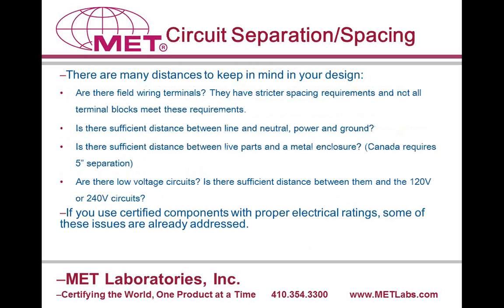Now, part of your design will include what's called electrical spacing. That's the separation between your live parts, your live and neutral, your live and ground. There needs to be a certain distance between these components. If you have a field wiring terminal, the spacing requirements tend to be greater because of the possibilities of loose wires. And this is one of the places where having a certified component like a terminal block comes in handy because the spacings are already certified. However, if you're designing a circuit board, it's critical that the board be laid out with proper spacings, and this is one of the things that we'll be measuring when we inspect your equipment.